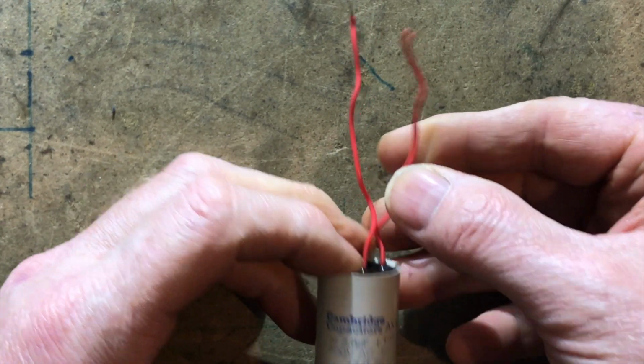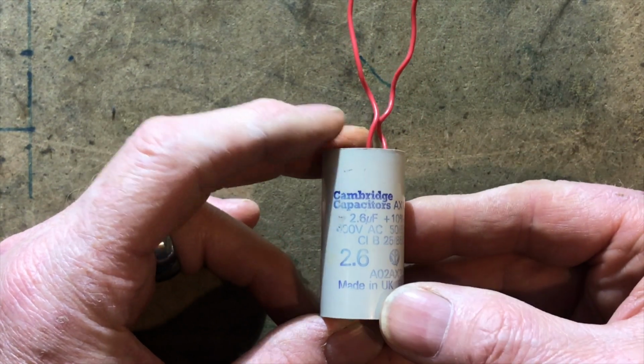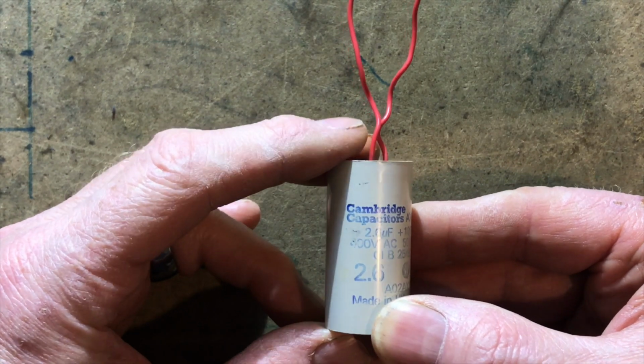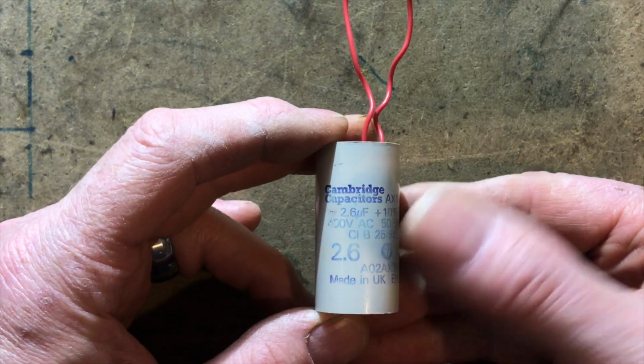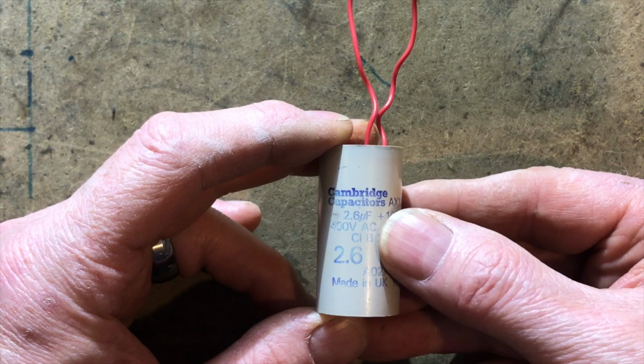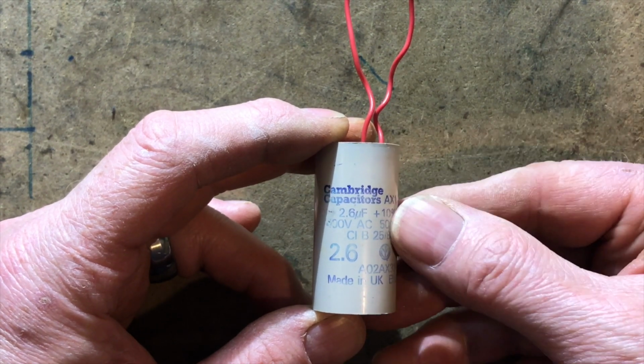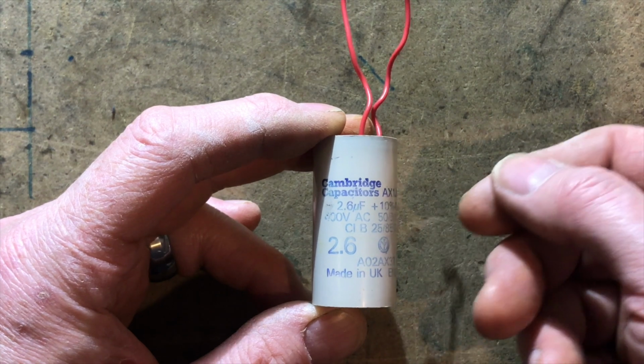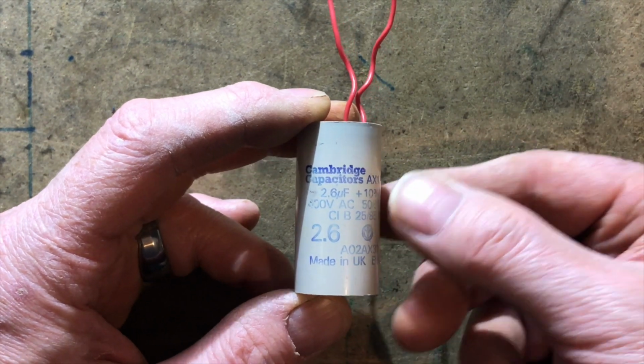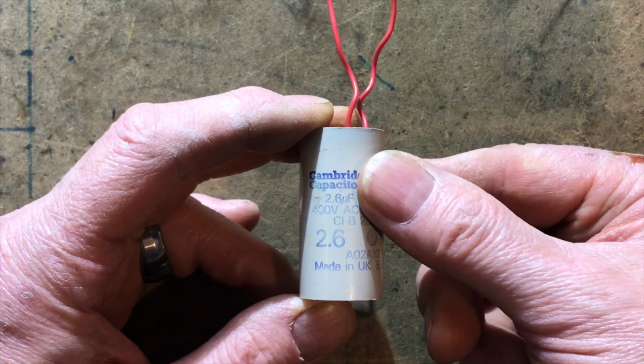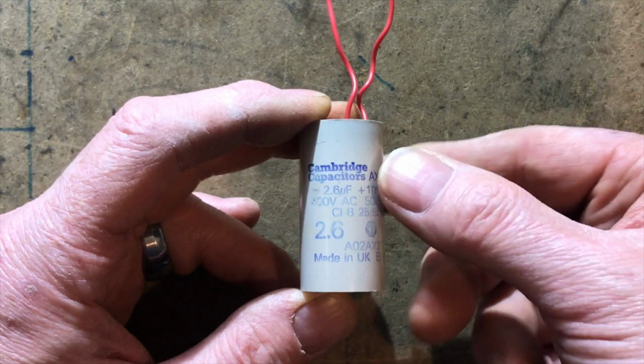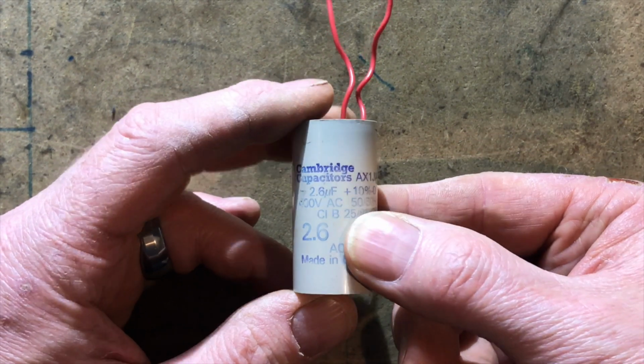So it dissipates its energy through these two wires here on startup, and then recharges itself while the pump is running. So you could have a fault on the pump where the pump won't start, but if you take the bleed screw out and spin the shaft and the pump starts running, then there's every chance this start capacitor has gone, because this is only here just to start the actual pump.